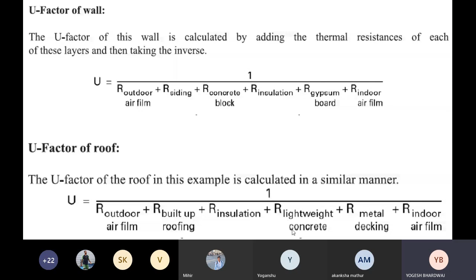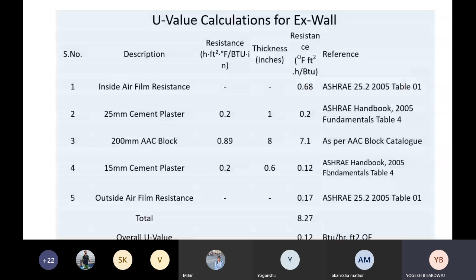This is the resistivity in the second column. There is the description, this is the material. In the third column, it is the resistance. If you multiply this with thickness, you will get the overall thermal resistance. And then if you add all the R values individually, you will get the total R value. If you take the ratio of 1 divided by total R value, you will get the overall U value. We use the U value to evaluate the heat load through walls, roofs, and glass, the conduction heat.